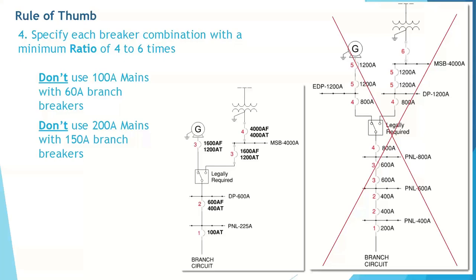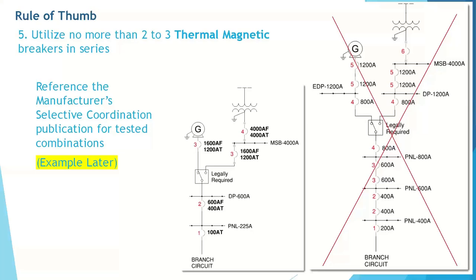For 3D, we may need to specify all breakers, including parallel loads that don't require code-enforced selectivity with electronic trip units and ZSI. We will define these parallel non-code-enforced loads later on as last-in-line breakers for ZSI. The fourth rule of thumb is for ratio. Try to design your system with a minimum ratio of 4 to 6 times between levels for the breaker. You don't want to use 100-amp mains with 60-amp branch breakers. You want to shoot for at least a 4 times ratio. The final and fifth rule is to reduce thermomagnetic breakers in series as much as possible, no more than 2 or 3. You will likely also need to reference a manufacturer's selective coordination publication for tested combinations of these breakers.